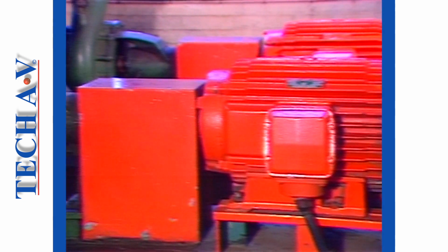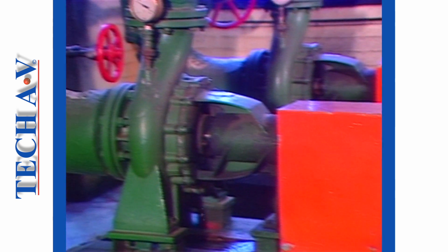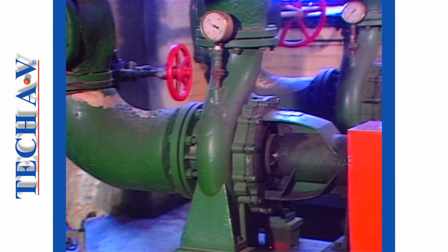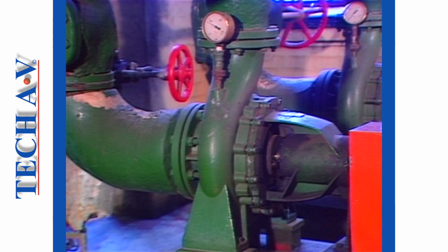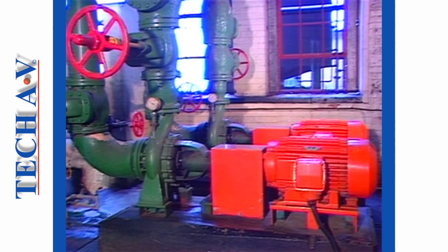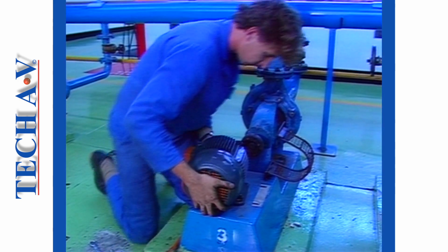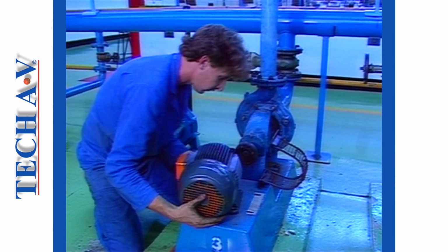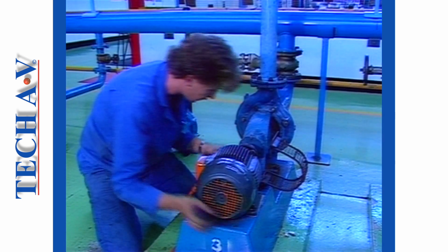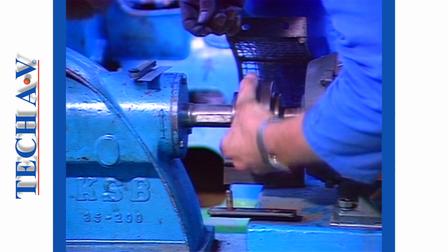When any pump is installed, we refer to the whole assembly as being a pump set. A complete pump set comprises the pump itself, together with its drive unit. Both pump and drive unit are mounted upon a base. Most larger pumps are separately mounted from the drive unit. The drive unit is connected to the pump shaft by means of a coupling.